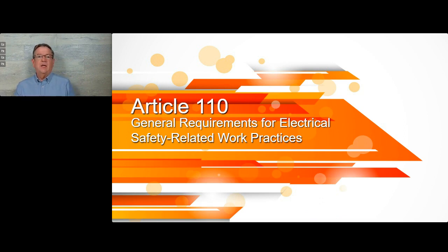Now, Article 110 in NFPA 70E, I know probably a lot of you are somewhat familiar with it, or a lot of you are really familiar with it. It's really well organized. There are three main chapters, Chapter 1, 2, and 3. The bulk of the requirements fall under Chapter 1, and Chapter 1 is broken up into 100 definitions, 105, which doesn't have a whole lot in it anymore. But the main parts of this are Article 110 and 120 and 130. And that's what I want to talk about. I'm also going to talk about a few changes that have occurred in Chapter 3 and a new edition of another informative annex. So a lot of major things have happened.